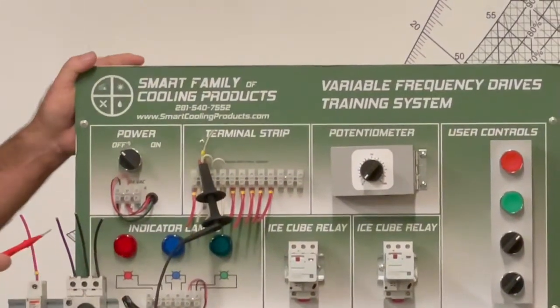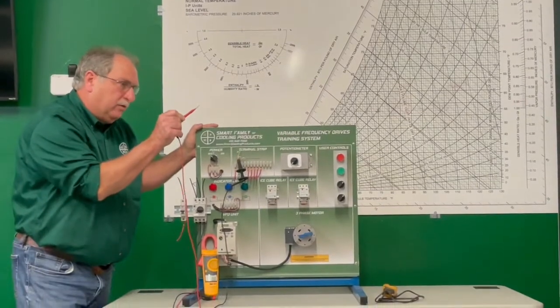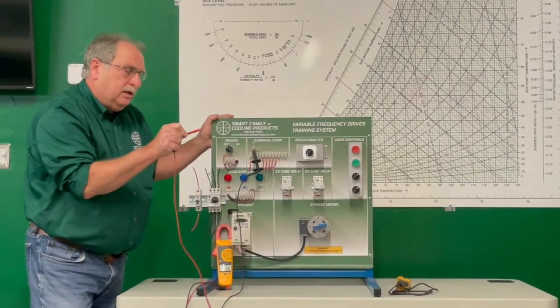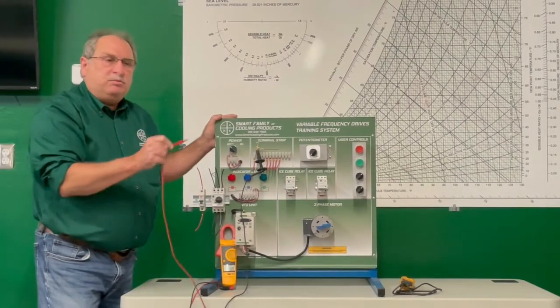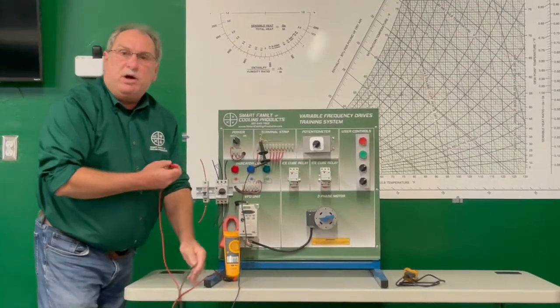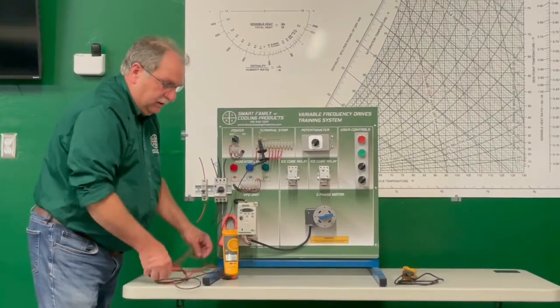Oh, I don't have it on five. So then you can look at your schematic and see, okay, I'm following the circuit path. And I see where four is and I see where five is, but I don't have it on five. So I can look at the schematic and I can identify what component that is that stopped the flow of electricity.